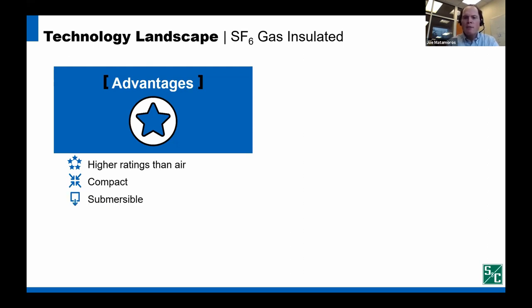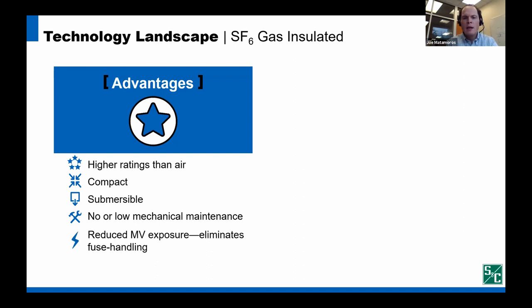As mentioned, a key benefit for sealed gear is that it can be operated submerged. Since the active parts are inside a hermetically sealed tank and protected from the environment, there is no regular mechanical maintenance required, unlike other technologies like a medium voltage breaker that would need to be racked in and racked out for maintenance. The next benefits are improving worker safety.